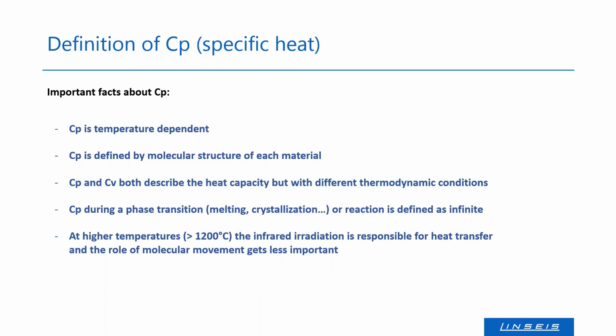What's also important is that CP is often hard to measure at really high temperatures. Here, infrared irradiation is the main heat transfer, and no longer the heat transfer between the sample crucible and the measurement system. So it's hard to detect valuable CP values, but most DSCs, or the standard DSCs, are limited to 600. So it doesn't matter much here, but of course at 600 or 700 degrees it also has an influence.